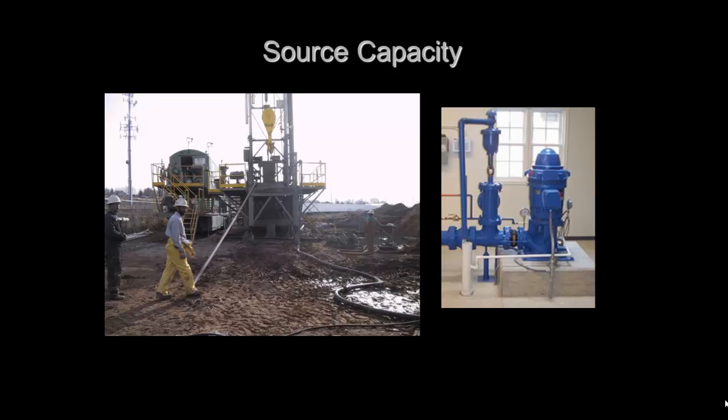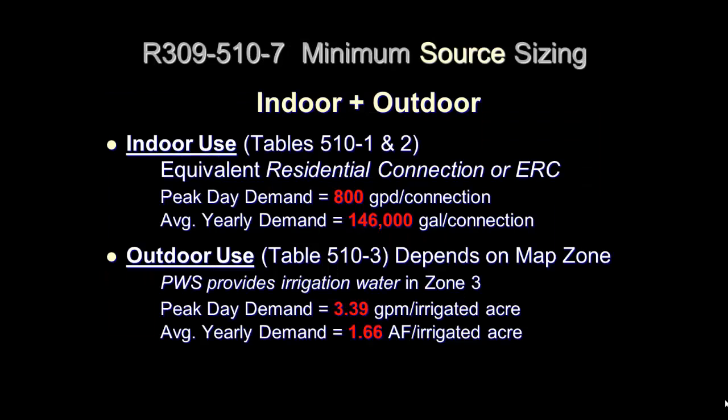We'll now cover the requirements for source capacity. Drinking Water Rule R309-510-7 provides the requirements for minimum source sizing. This includes indoor and outdoor demands. Tables 510-1 and 2 provide the indoor use values for equivalent residential connections or ERCs. The minimum peak demand is 800 gallons per day per connection, or an average yearly demand of 146,000 gallons per connection. The outdoor demands are listed in Table 510-3. The zone is based on the location found on the irrigation zone map. The corresponding zone is now listed on the top header of the public water system report to reduce guesswork.